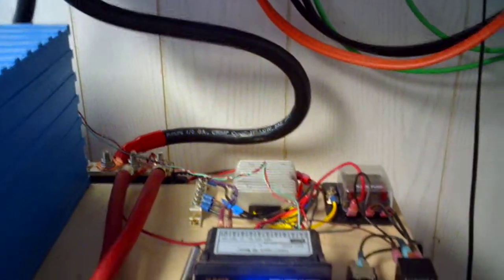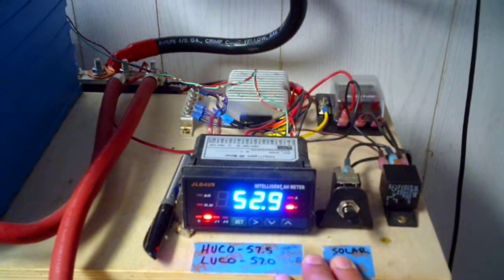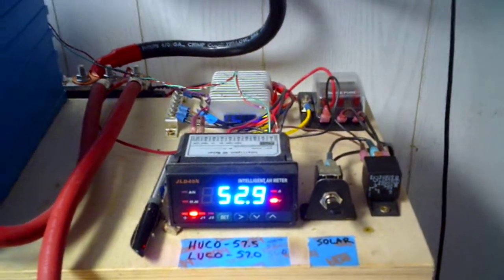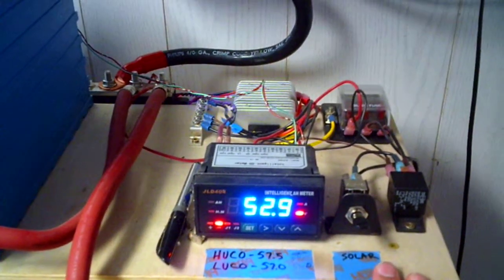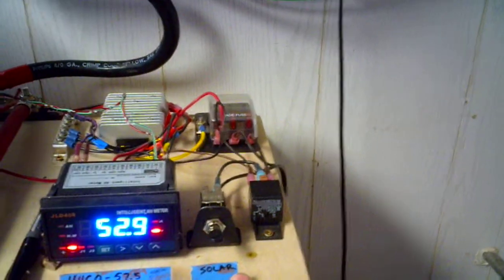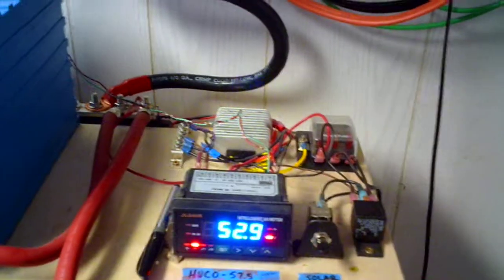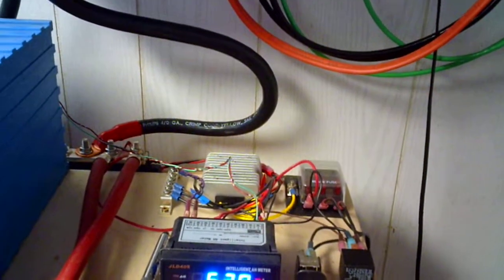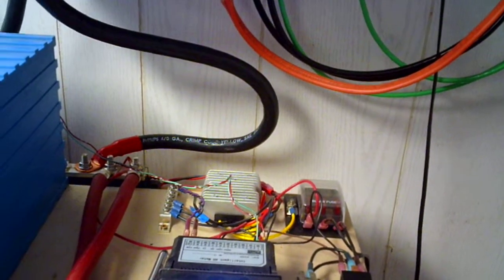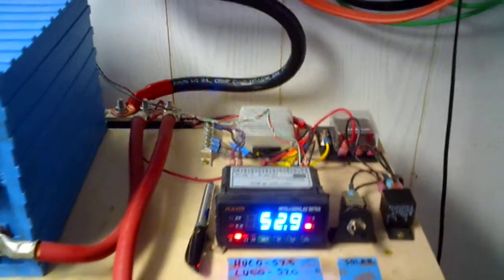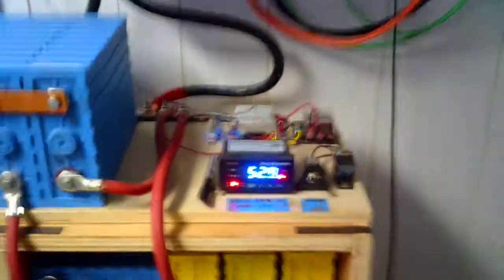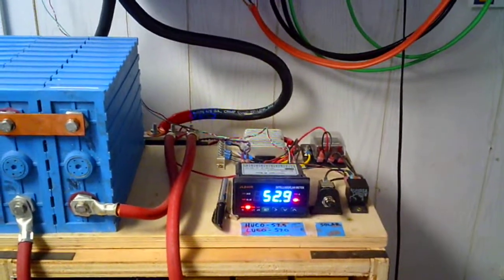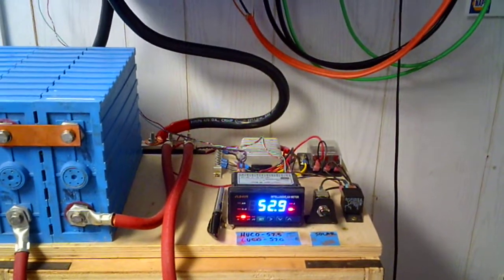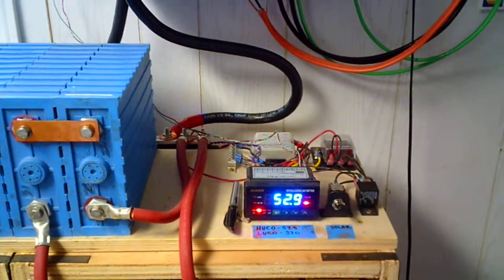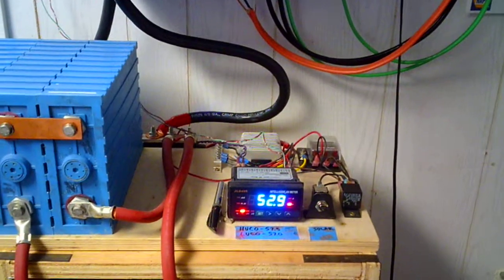Whenever that JLD sees 57.5 volts, it's got a little internal relay that will energize this relay, which goes out that line right there and sends 12 volts to a contactor that I've got outside in a box that will disconnect the solar panels from this system. So when that hits 57.5 volts, that contactor will trip, disconnect the power, disconnect that 50 Hertz to the grid-tied inverter, and the grid-tied inverter will shut down.